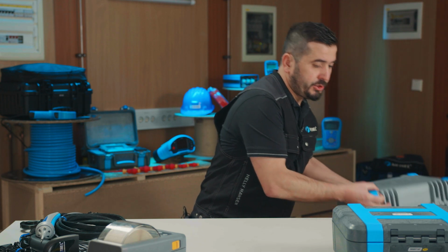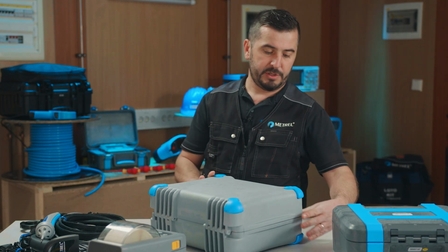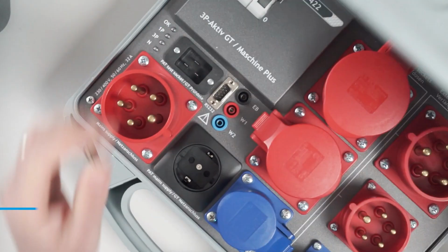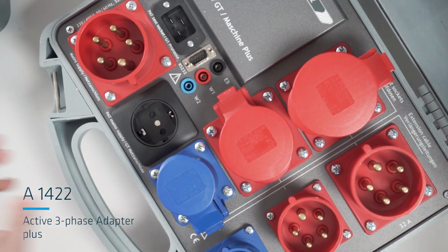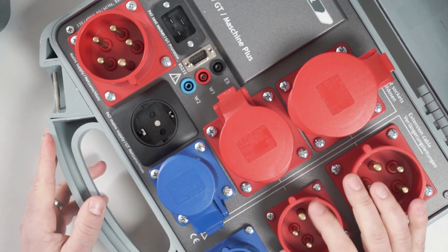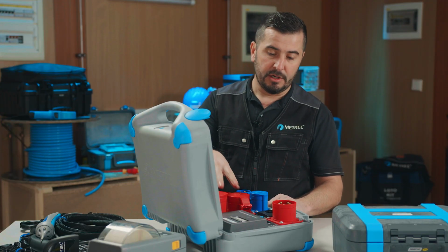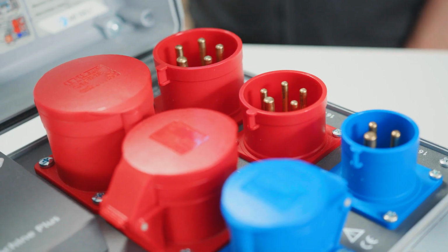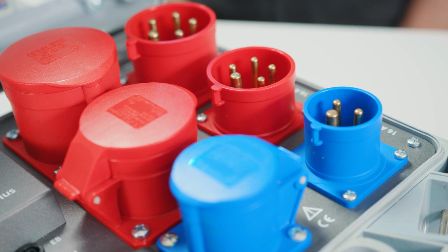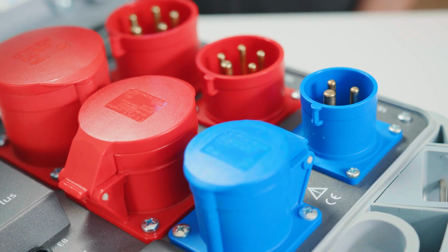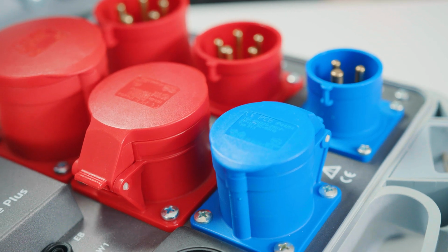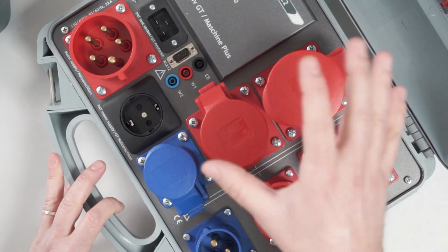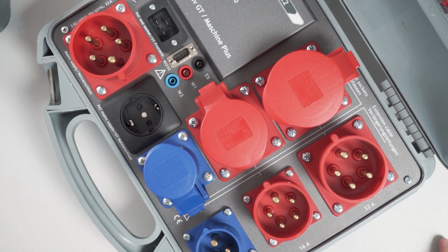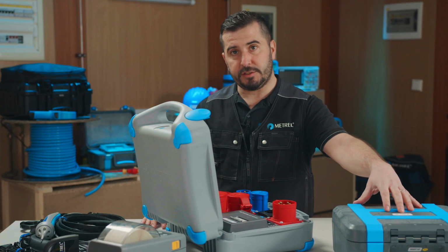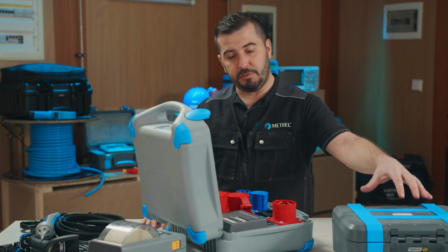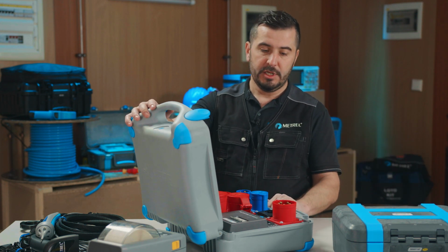The last one, about which I would say a couple of words, is this active three-phase adapter. The active three-phase adapter is available in two options. This one covers everything. The smaller brother of it doesn't cover welding equipment testing, so this one is for all three-phase appliance testing plus welding equipment testing. As mentioned in some video before, you can connect it to the test instrument. The test instrument is then the master instrument, which is controlling all measuring functions of this three-phase adapter.